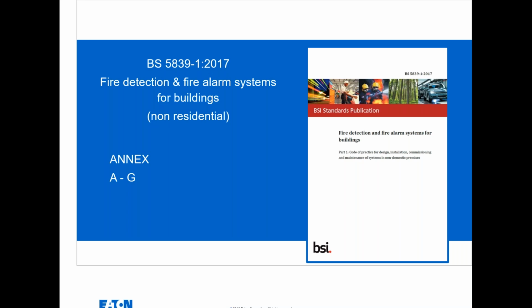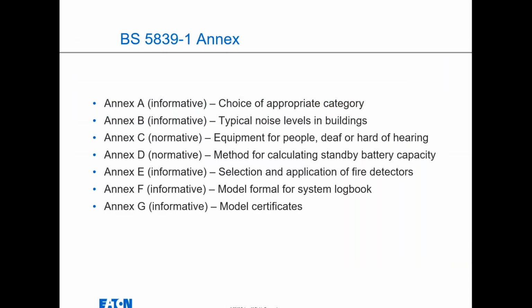So these are just some of the annexes, A to G, which give you some guidance. If you do pick up the standard, you can look at choice of appropriate categories, typical noise levels, as I touched on earlier, in buildings, that's background noise levels, any issues with equipment for people who are deaf or hard of hearing, method for calculating standby capacities, selection and application of detectors, and the model form of a logbook. And then obviously Appendix G is all the model certificates that form part of the standards.